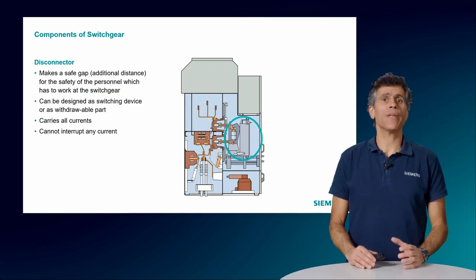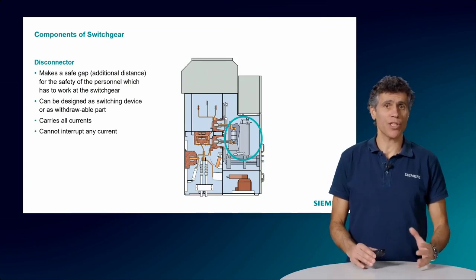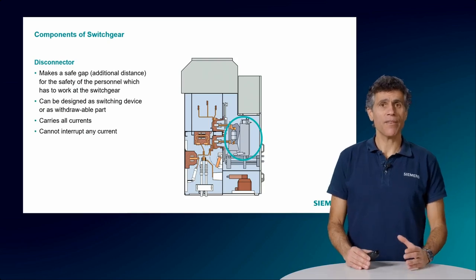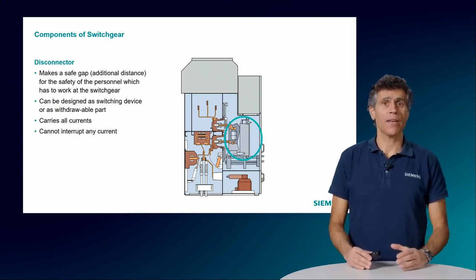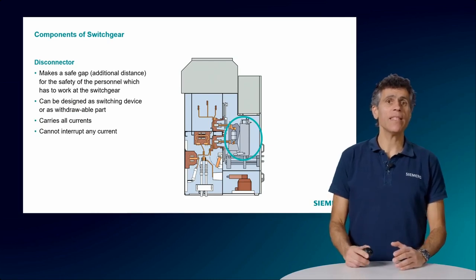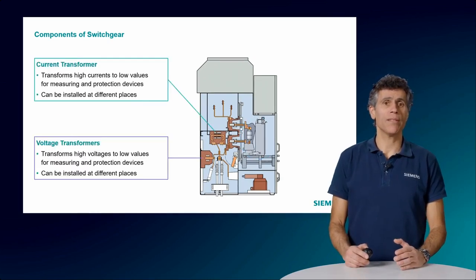They are used for creating a so-called safety gap for the safety of the personnel that need to work on equipment downstream of the switchgear. There are other devices that can be inserted in this compartment. We will return later to circuit breakers in more detail and also talk about some other switching devices and their duties. Let's now talk about other components, the transformers. These devices are placed on the medium voltage path, and their function is to provide information about the values of voltage and current flowing.